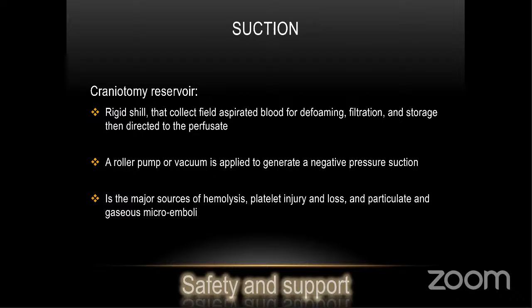The cardiotomy reservoir is a rigid shell that collects field-aspirated blood for defoaming, filtration, and storage, then directs it back to the perfusate.